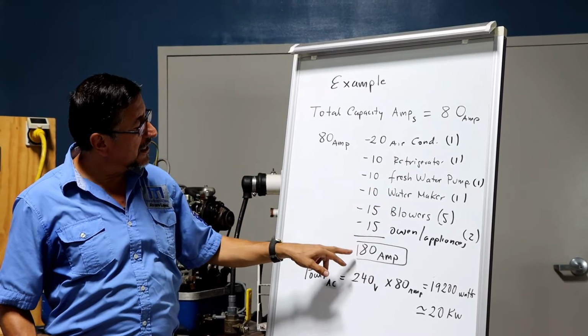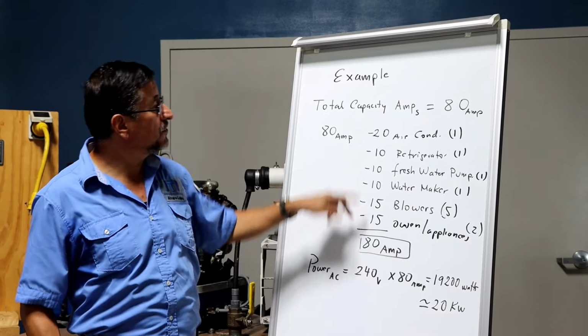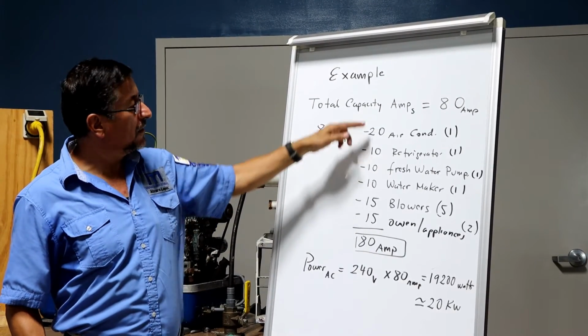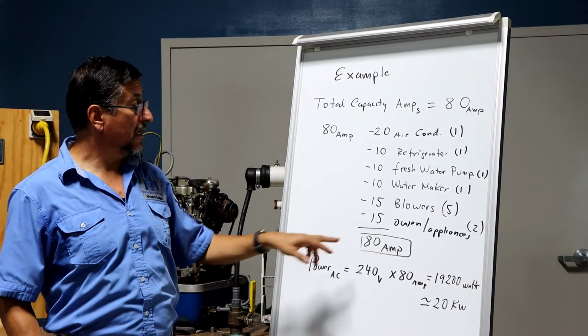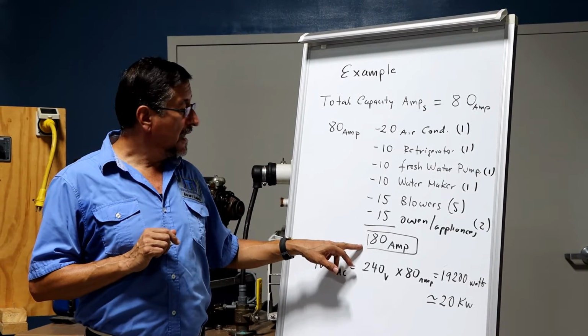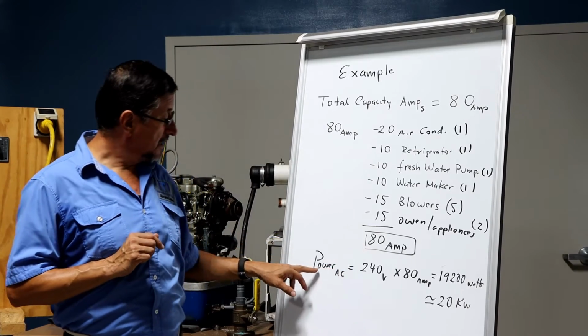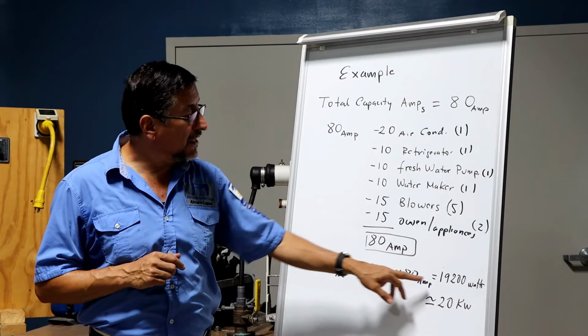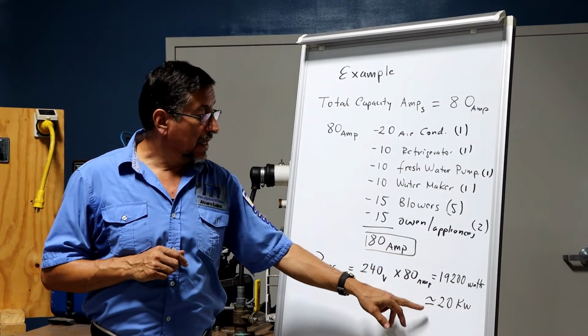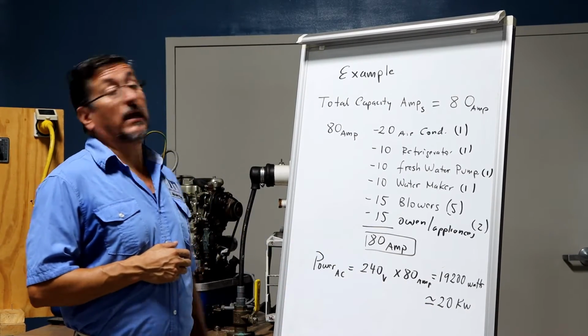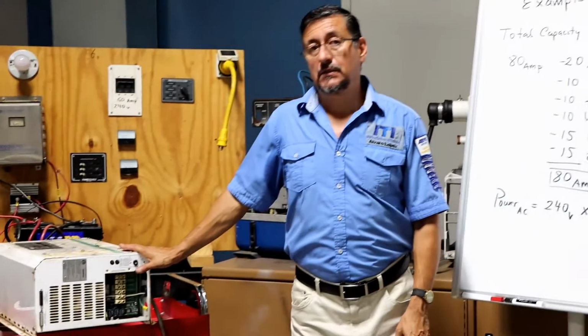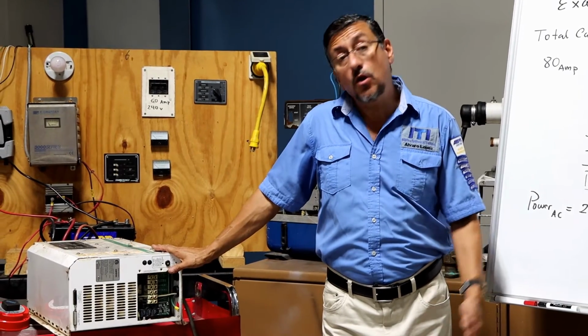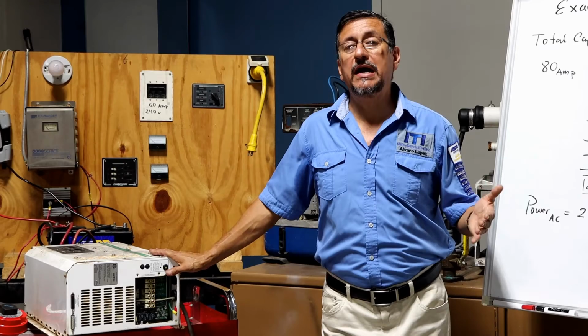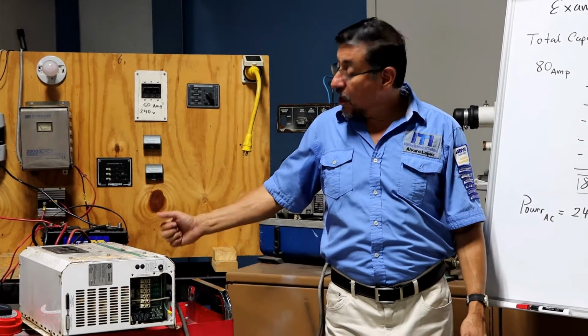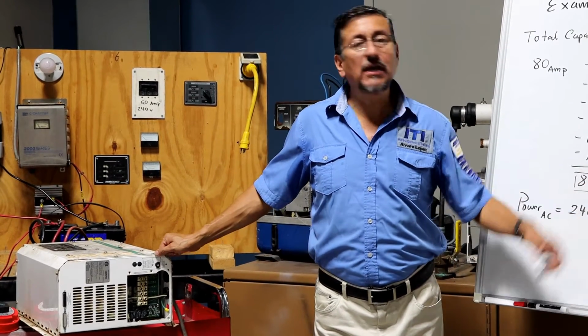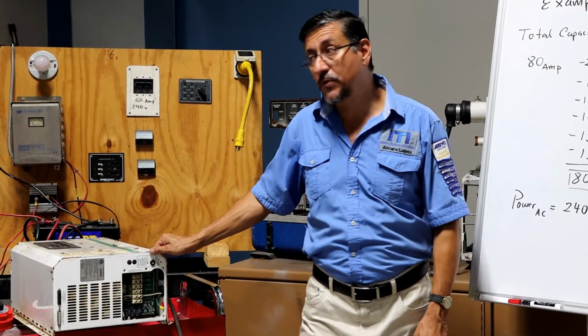Those equipments in total need 80 amps. 20 for the air conditioning, 10 for the refrigerator, 10 for the... In total, 80 amps. Okay, if the boat is double phase, 240 volts, and the amps are 80 amps, how much power do I need? I need 240 volts times 80 amps. I need 19,200 watts. I need 20 kilowatts. Oh, I need an inverter of 20 kilowatts. An inverter of 20 kilowatts is an expensive inverter. Okay, but no problem. The customer approved buying an inverter of 20 kilowatts. And now I need to know how many batteries I need to supply 20 kilowatts for 1 hour, 2 hours, 3 hours. This is the procedure.